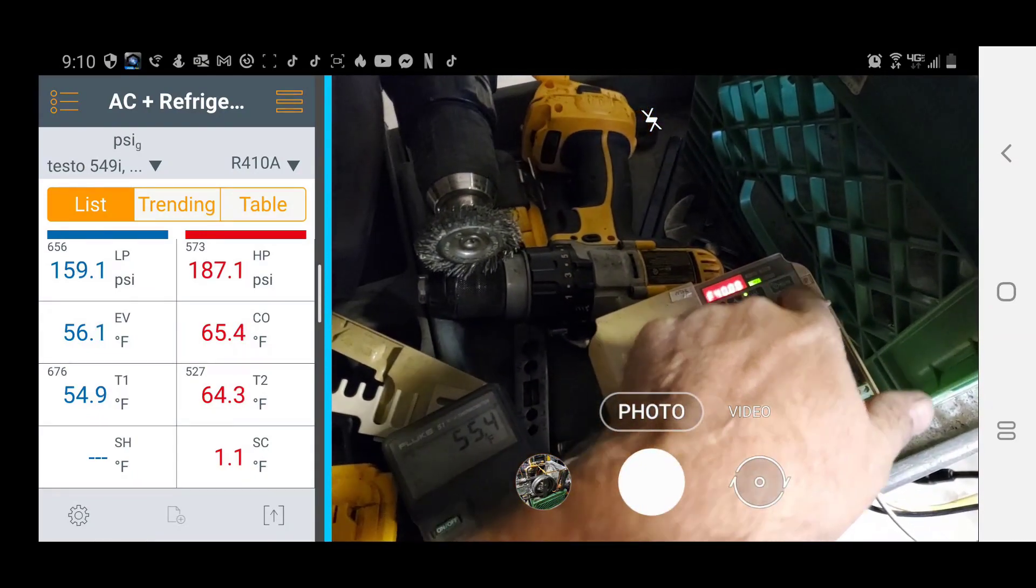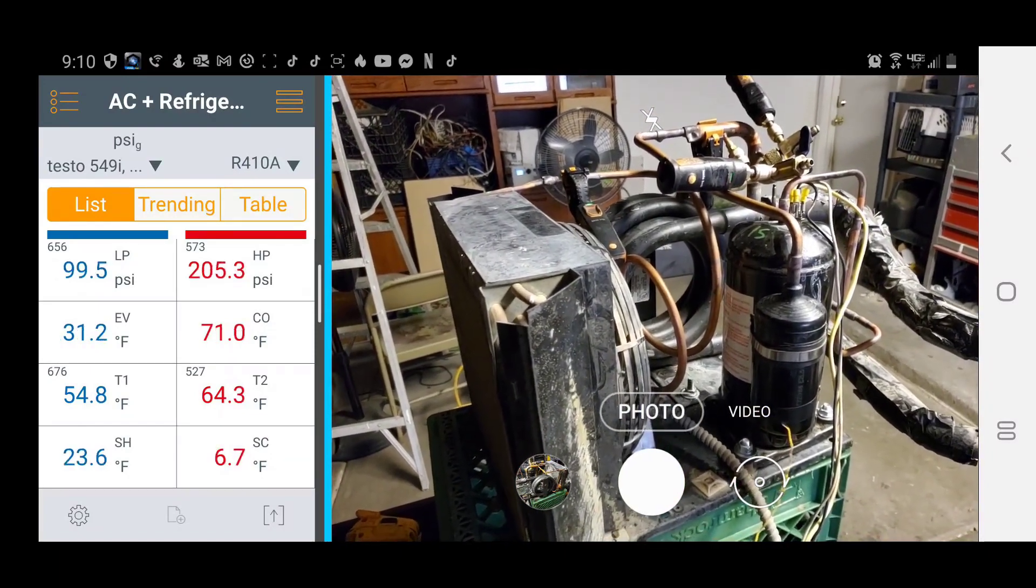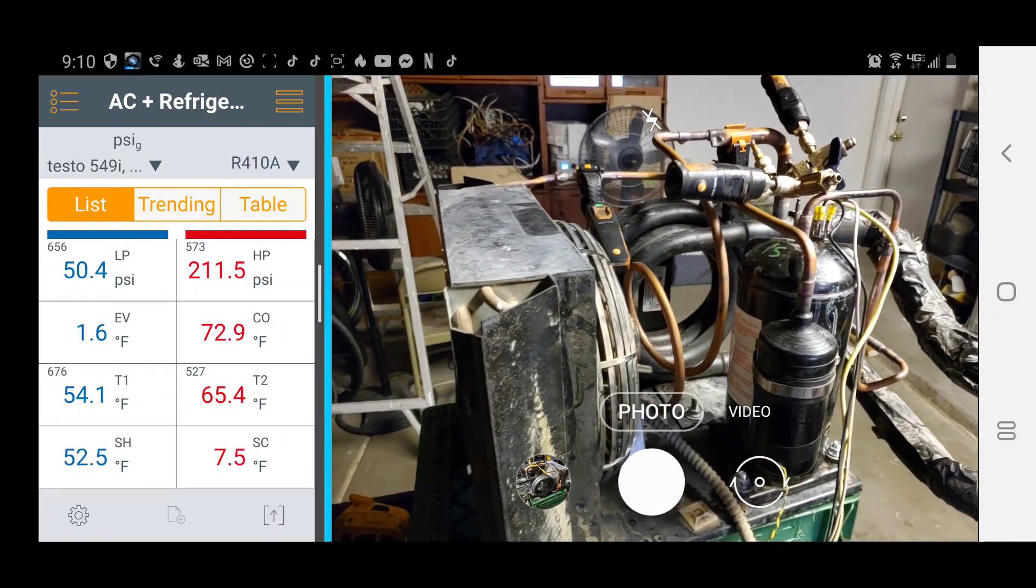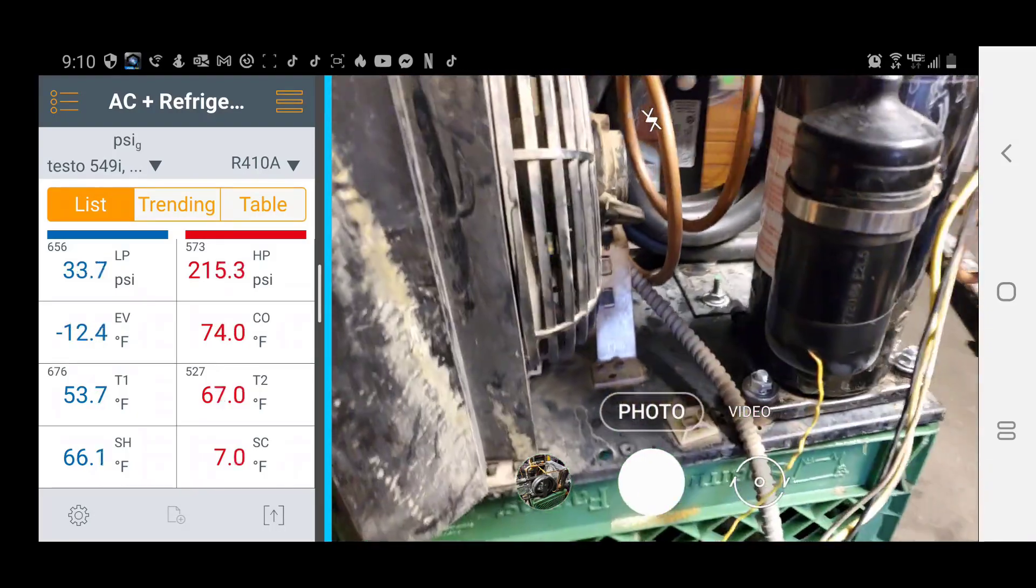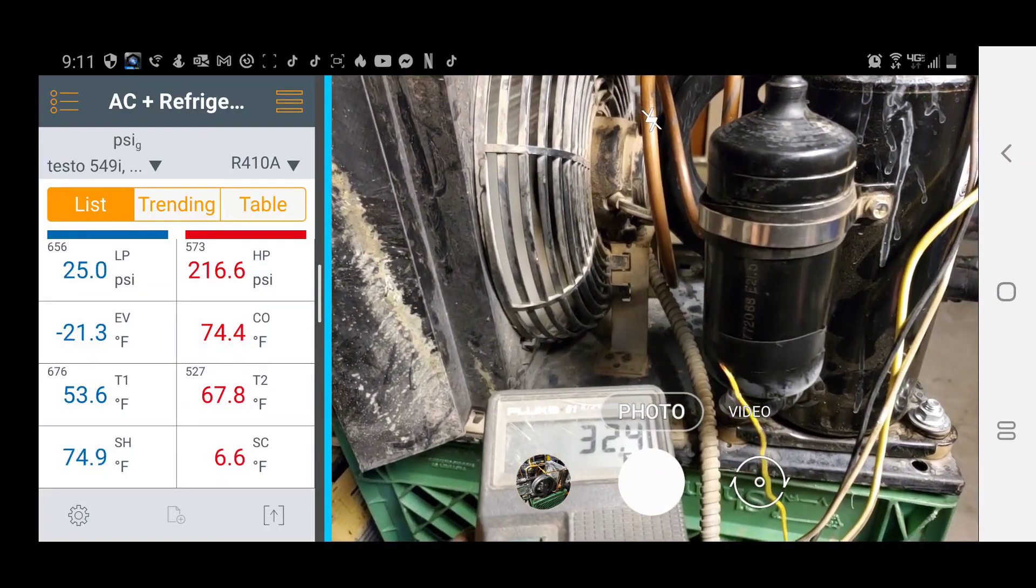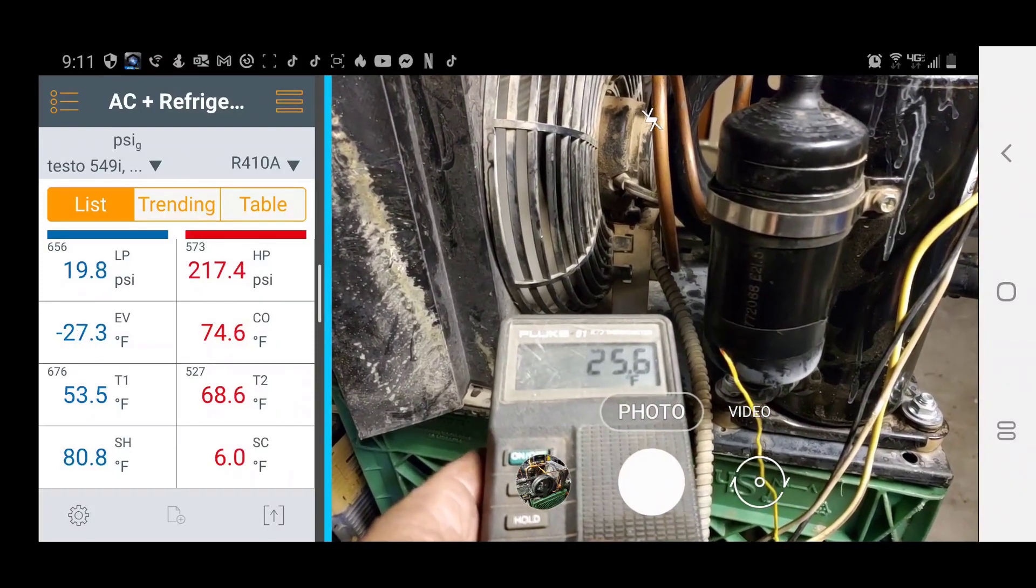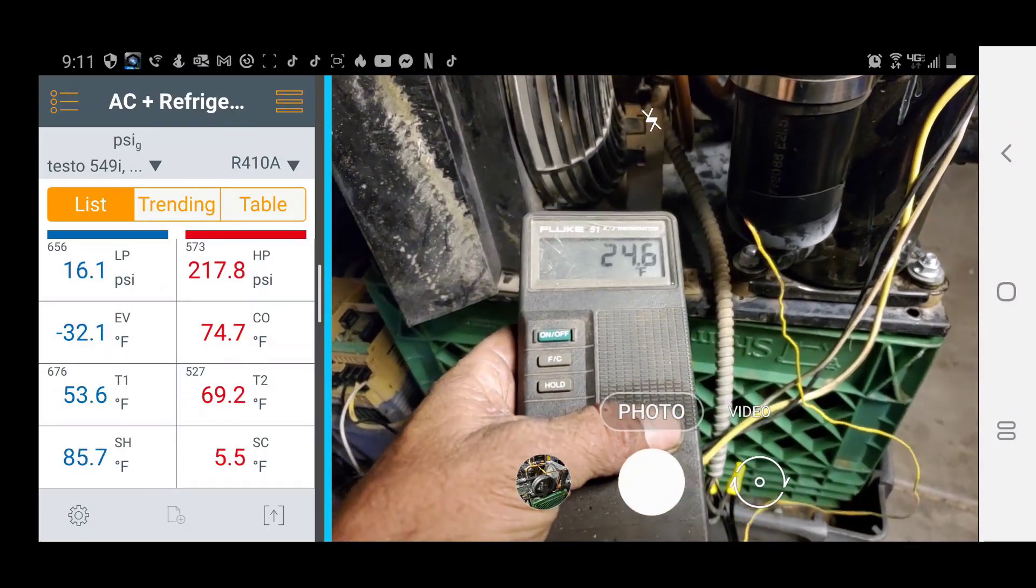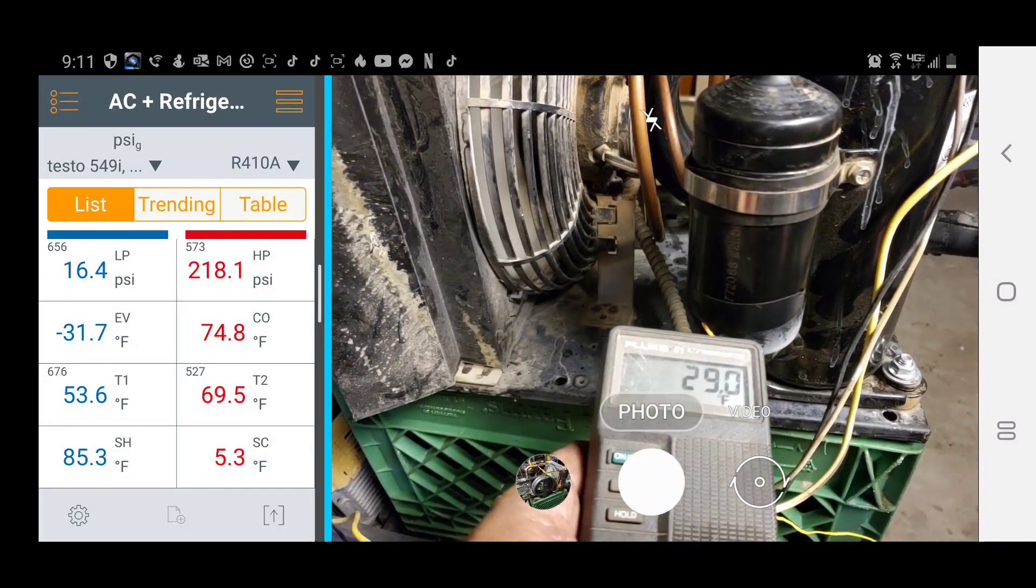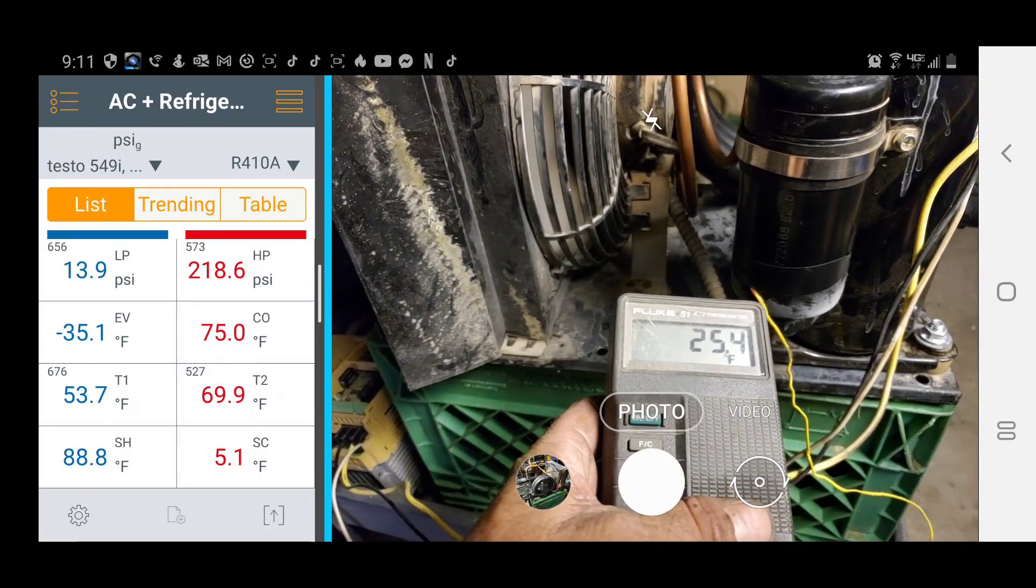So it goes back up to room temperature, 55. I'm surprised. I'm going to run it. See the pressures there. And it gets choked down on the suction because I have the pinch-off tool on it right before it goes into the capillary tube. But then yet look at the accumulator temperature—it's going to drop like a rock and you're going to see frost develop. Look at that. See, my suction line's pretty much the temperature of the room, 53 degrees, and I'm really starving the suction pressure which is taken right here. It's 16 PSI. I think it's rough, but yet when I restart it, it's like it's boiling off liquid. You'd think it would all be boiled off after a little while, but it doesn't. 28 degrees down there.